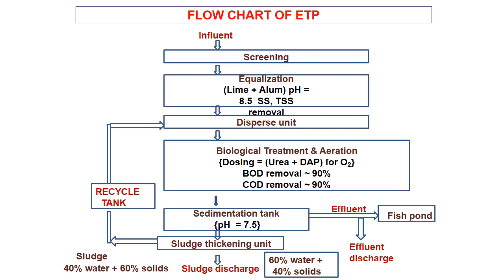Here we can see the complete flow of operation in the effluent treatment plant. There is influent, screening, equalization and mixing, then pH adjustment, and dispersive mixing. It goes for biological treatment — aerobic or sometimes anaerobic — and chemicals are added. BOD and COD are reduced by 90%. Then it goes to the sedimentation tank. The pH is checked and treated water is discharged to water bodies or fish ponds. The thick sludge undergoes thickening treatment, water content is reduced, and the thick sludge goes back for recycling in biological treatment.